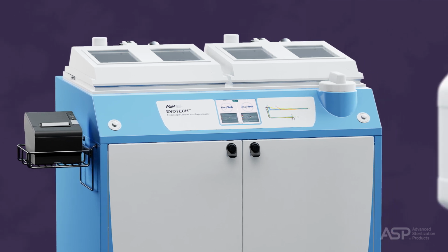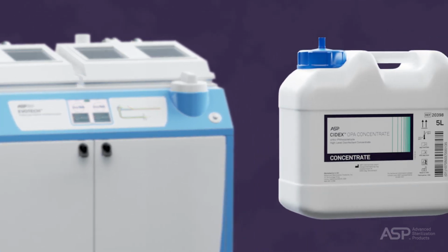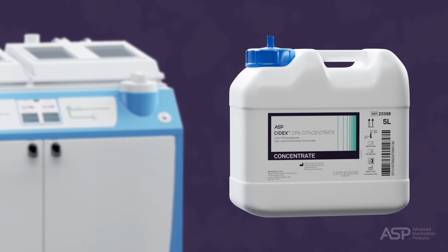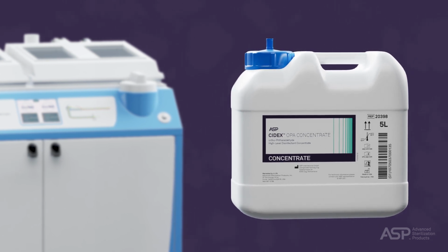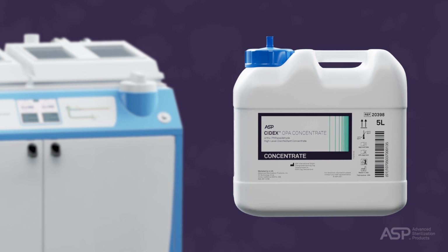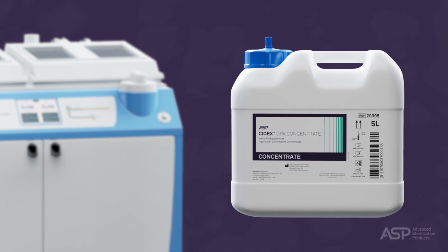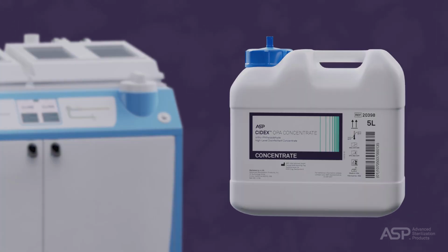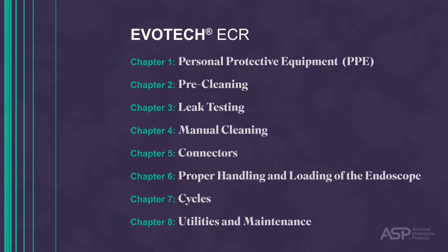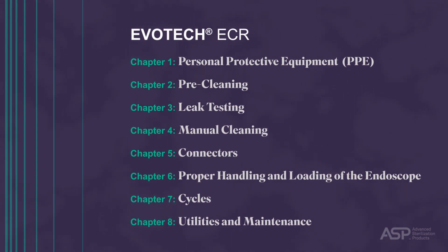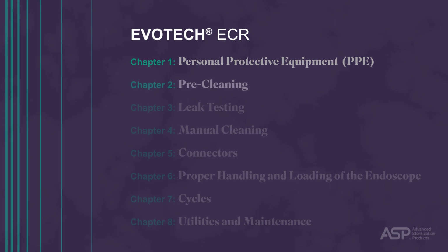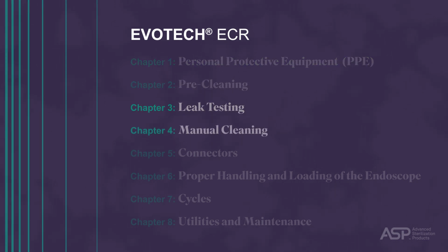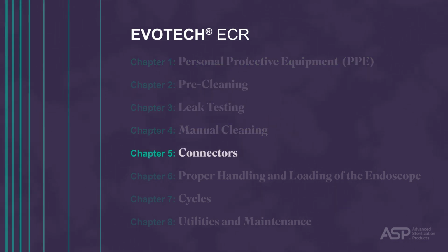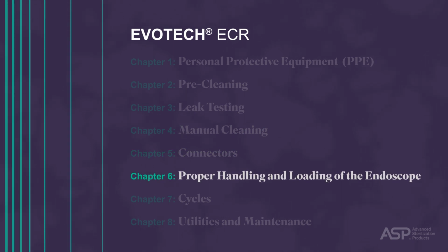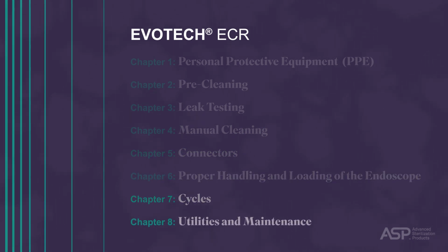High-level disinfection requires that the system be used with CIDEX OPA concentrate solution according to the instructions for use. This system has been validated by ASP and has been cleared by the FDA for use with CIDEX OPA concentrate solution. In this video, we will provide an overview of the EVOTECH ECR covering personal protective equipment, pre-cleaning, leak testing, manual cleaning, connectors, proper handling and loading of the endoscope, cycles, and finally, utilities and maintenance.